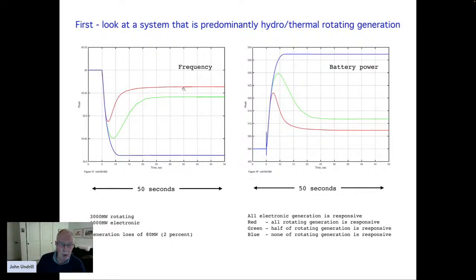Nowadays, of course, this is not done by young engineers walking around turning hand wheels. It's done by digital computers operating automatic generation control, which is considered to be secondary control, supervising the operation of the primary controls, which are governors. A load event occurs, frequency dips, governors respond, stabilize the frequency at a slightly reduced value, and then secondary control brings it back up. So the system sits stably, an event occurs, power starts to increase according to primary control, comes back to an elevated but not sufficient value, and then secondary controls bring it up to the amount that it finally needs to be. And the time scale is 50 seconds or a minute.